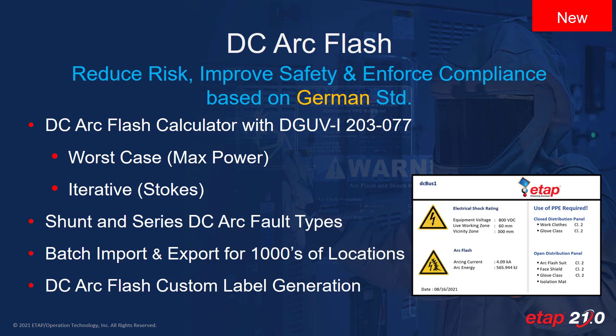The German Electrical Accident Insurance Institute has updated their standard with two methods for calculating arc flash in direct current systems. For those familiar with ETAP's DC arc flash module, the new methods are somewhat like our maximum power method and Stokes and Openlander methods. The worst case method is a spin-off of the maximum power method, but is expected to be just as conservative if not more.